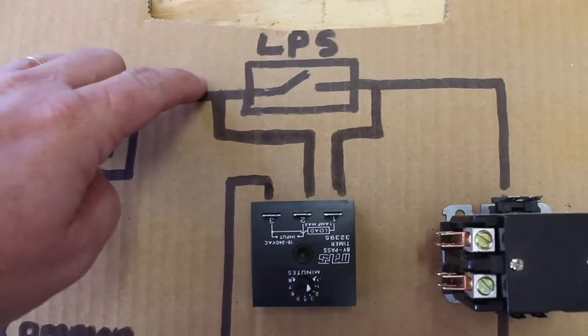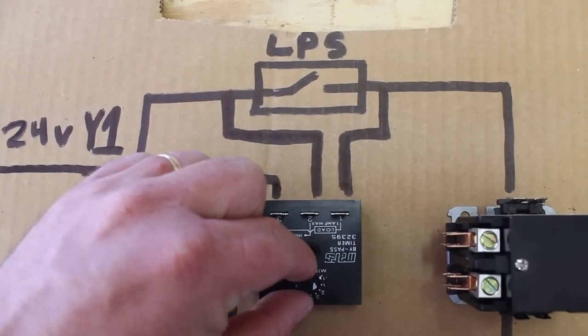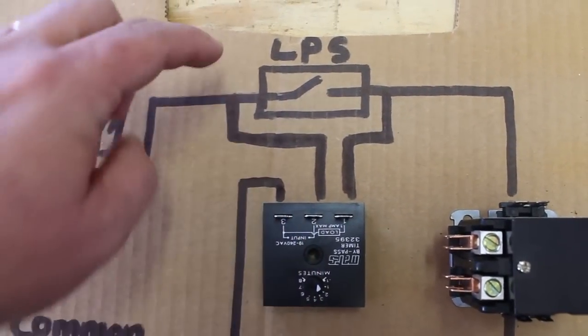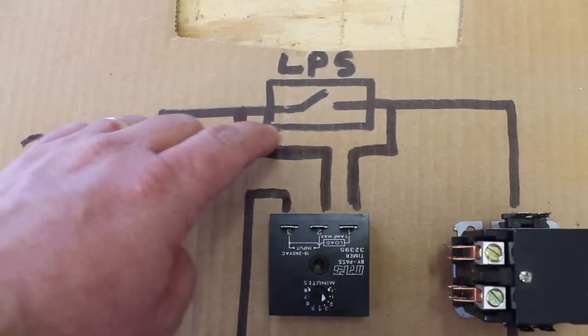When power is brought in on Y1, it starts the timer which is set between six seconds and eight minutes. For that time period, it will allow power to pass through, bypassing that switch.